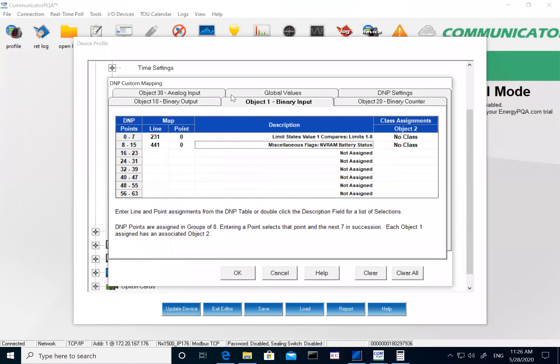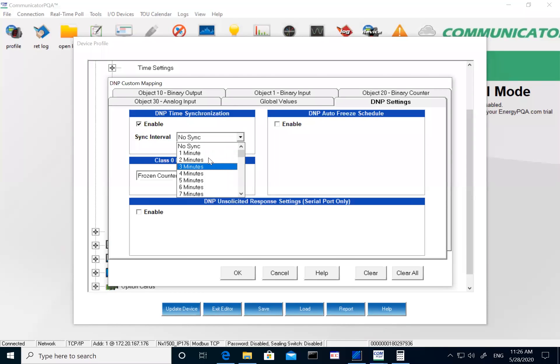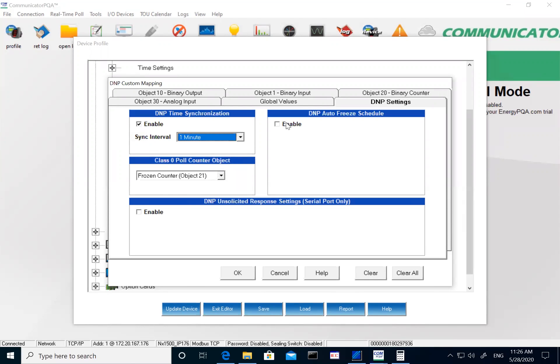The Nexus 1500 Plus has several options to sync the meter time: you can sync to a GPS clock, use NTP network time protocol to sync to your network, or use our software. You can also sync the meter time using DNP. If using DNP time sync, I would enable this and set up the interval for how often I want to sync — I'll leave it at 1. We also have a DNP auto freeze schedule.